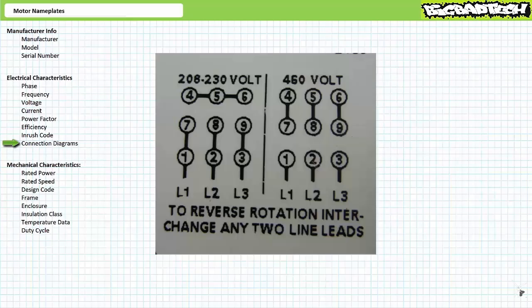Long story short, you get 0 points for creativity. Follow the connection diagrams exactly as illustrated, otherwise serious repercussions may result. As we learned in the electromagnetic interaction lecture available at the Big Bad Tech channel, polarity of the magnetic field is dependent upon current direction, and a motor might be damaged, or at the very least not work well if it isn't properly wired. Additionally, as we learned in the rotating magnetic field lecture, also available at the Big Bad Tech channel, swapping any 2 phases in a 3-phase AC system results in a reversal of the rotating magnetic field. Hook up a motor exactly as intended, and it will work as intended. Do anything else, and it won't. Again, the upcoming motor connection diagram lecture deals exclusively with this aspect of the motor nameplate.